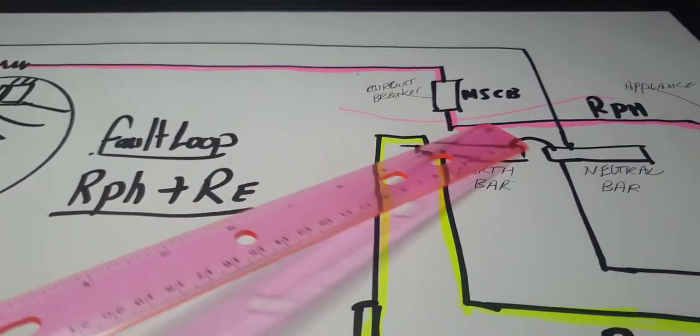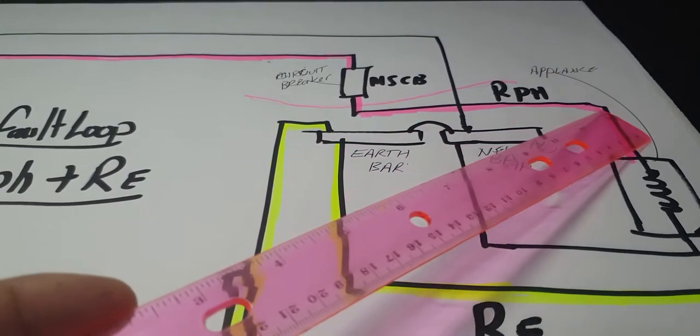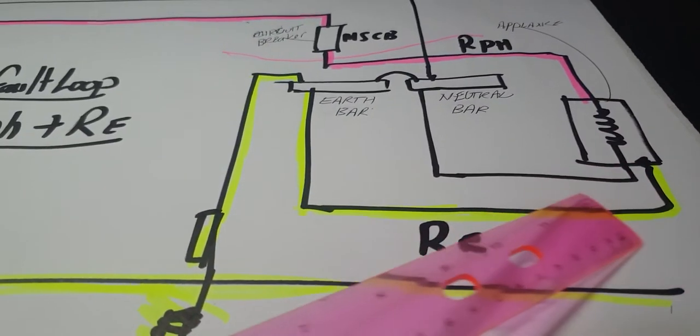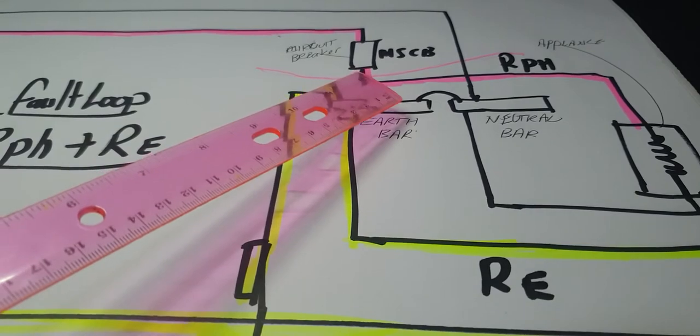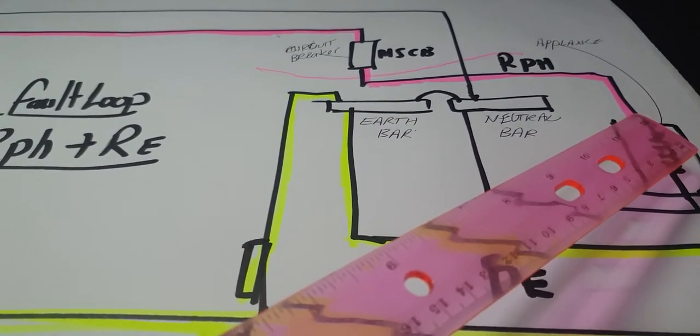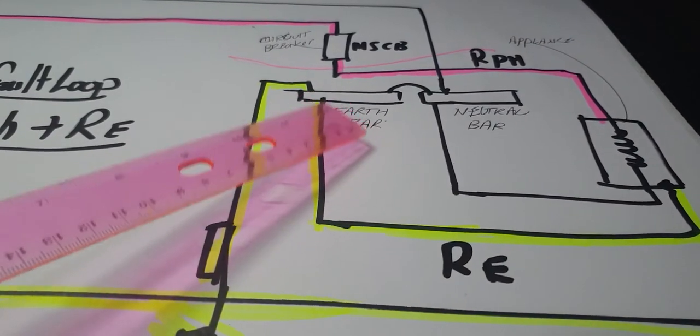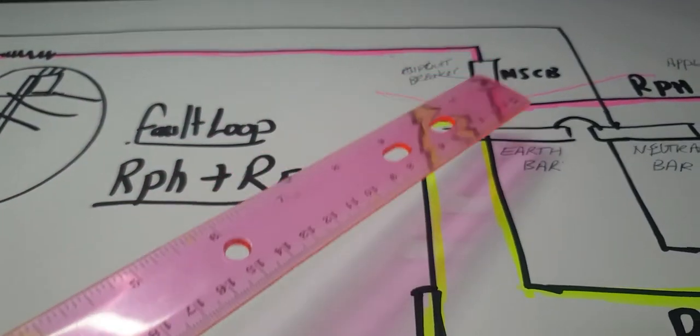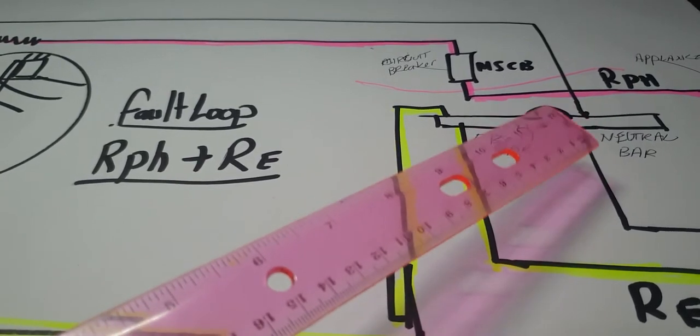Just to go back on the fault loop. When we talk about fault loop, we have the active, and then we have the earth. The definition for fault loop impedance is RPH. When we look at our graph in our book, we see RPH, which is not the red phase but the resistance of the phase and the resistance of the earth. Once we get to this point, this is so important. This wire coming into the top of the fuses out in the street is quite large.